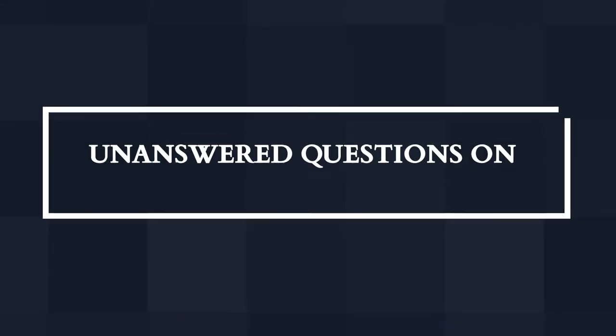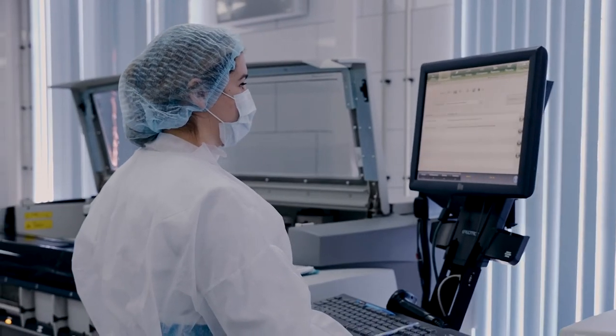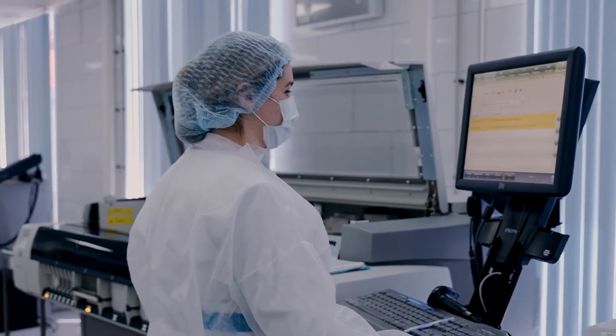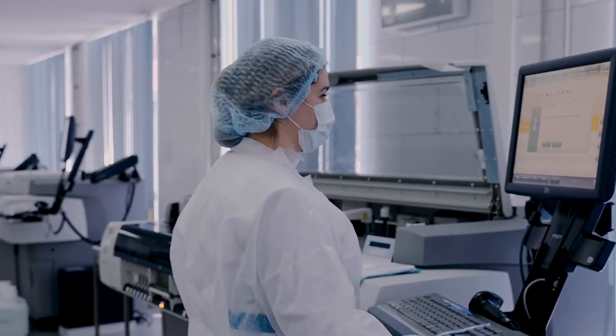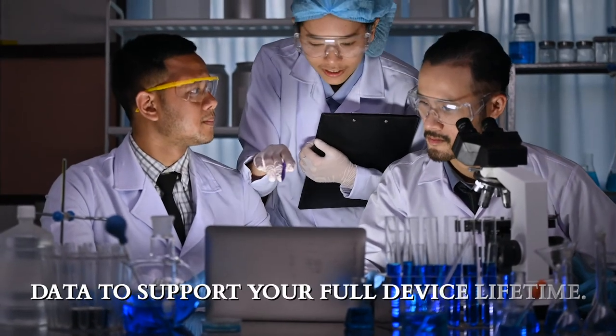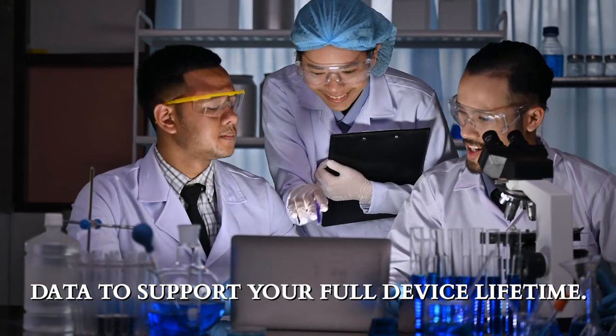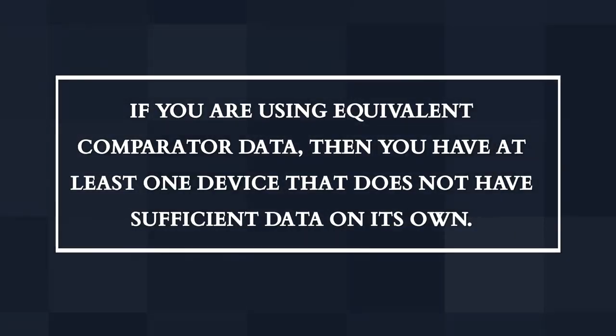The fourth bullet is the unanswered questions on long-term safety and performance. I do not have a definition for you on what long-term is — it varies, and there's a specification that goes into it. But you need to consider if you have data to support your full device lifetime. The last bullet: if you are using equivalent comparator data, then you obviously have at least one device that does not have sufficient data on its own.